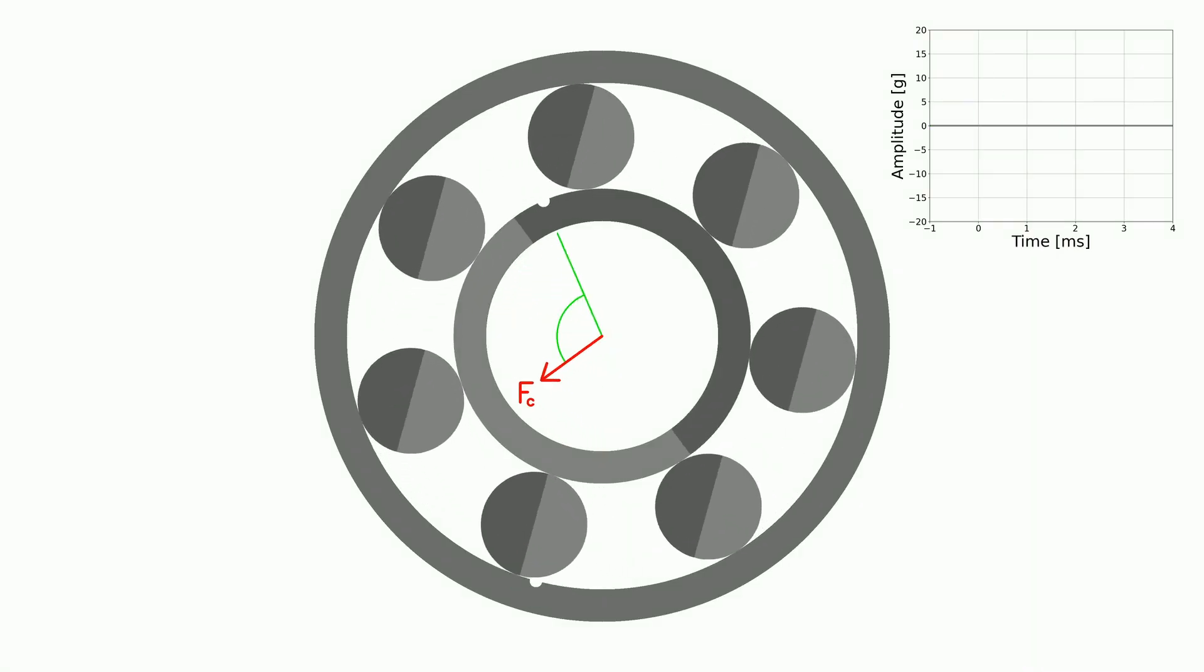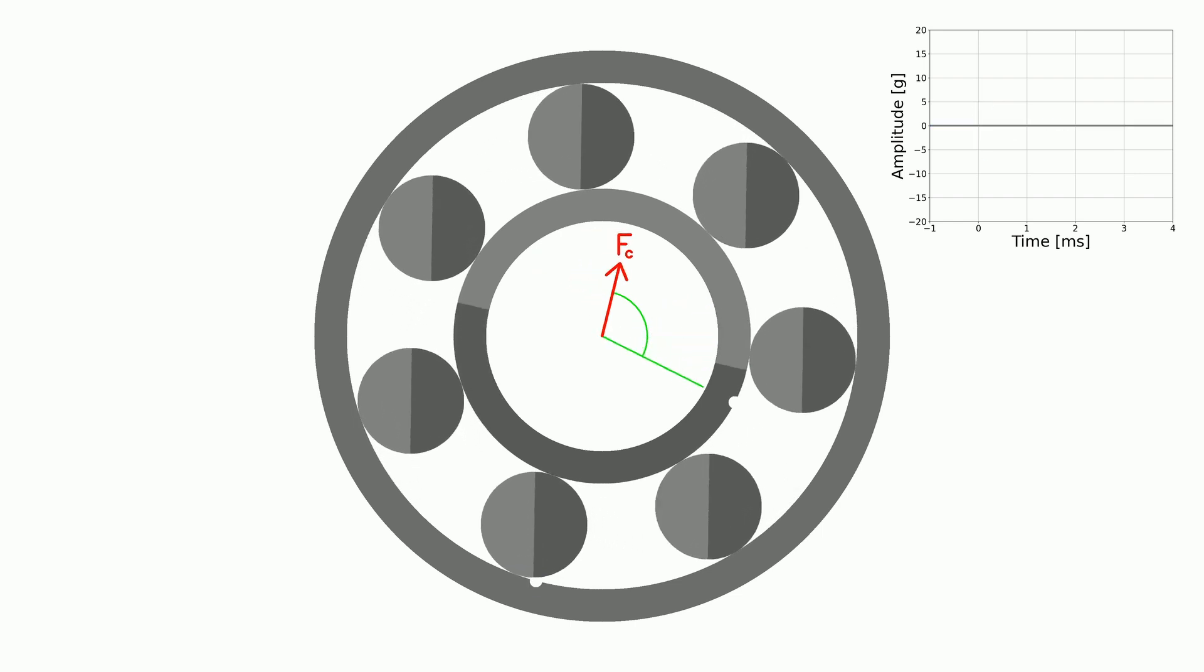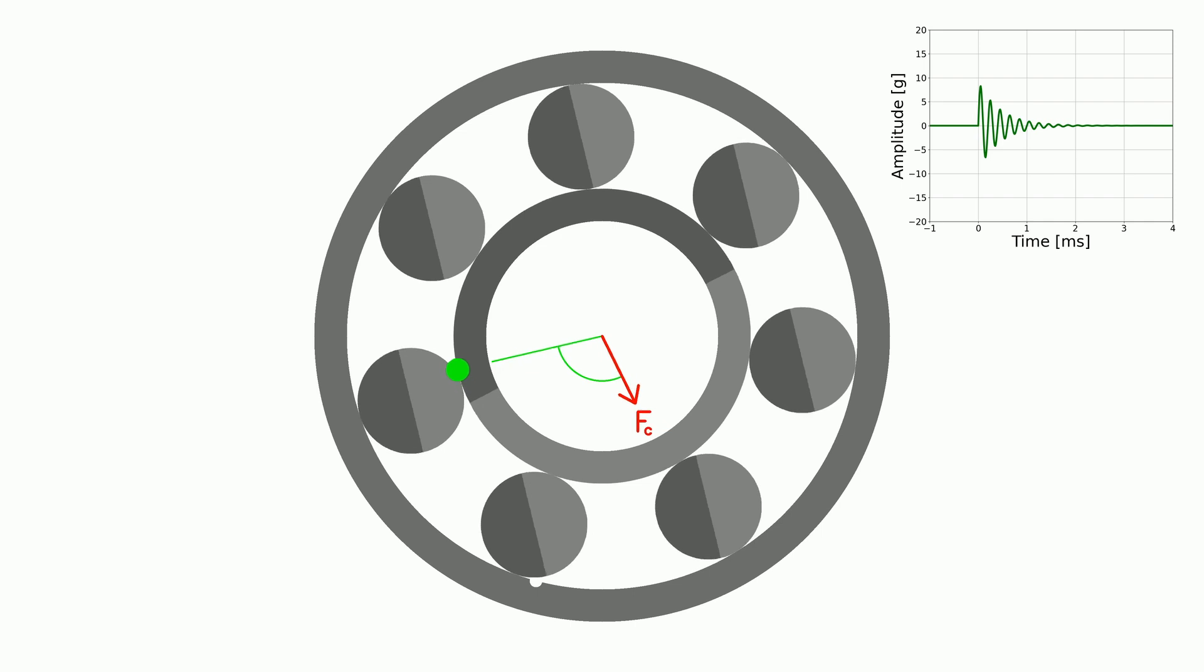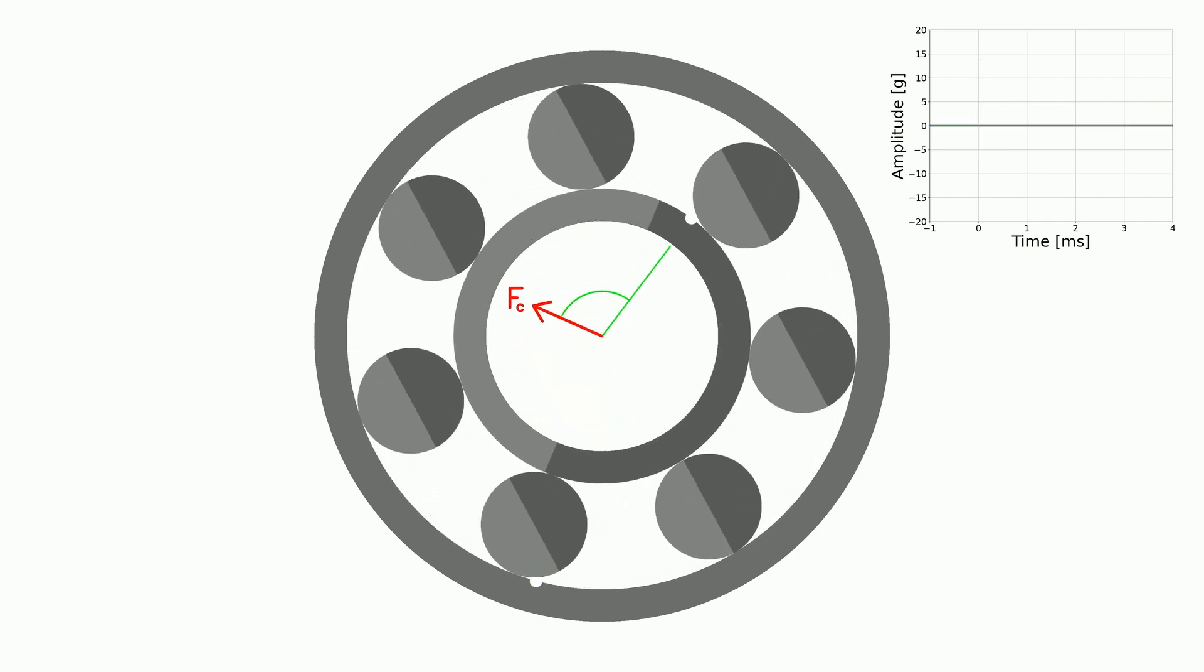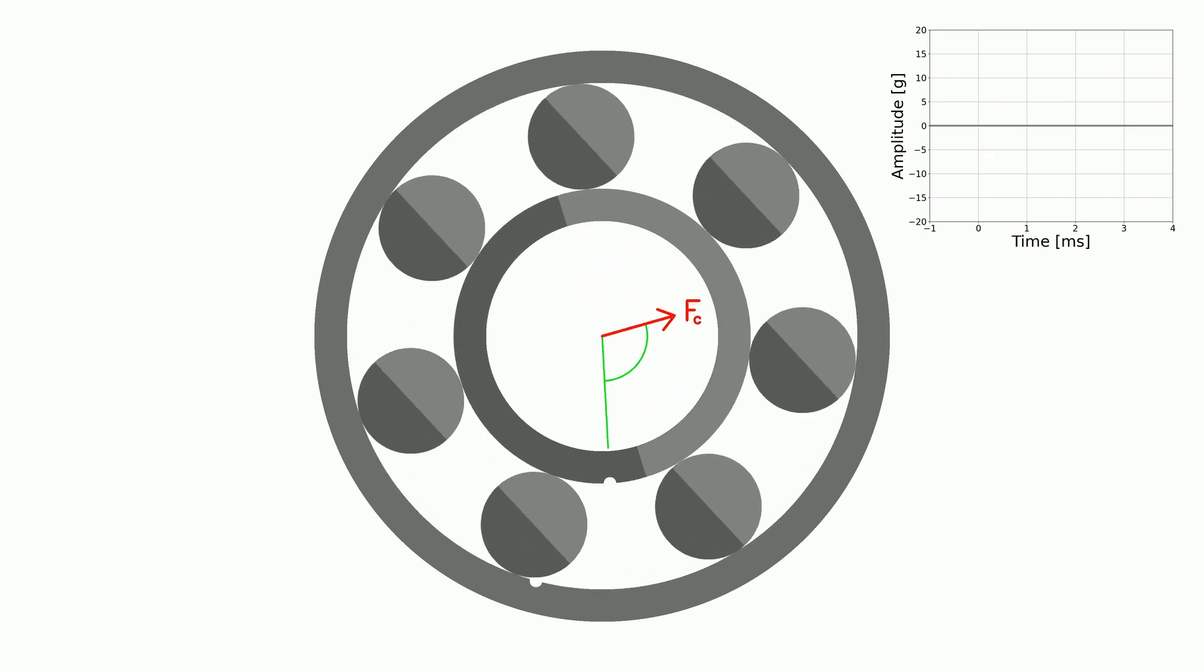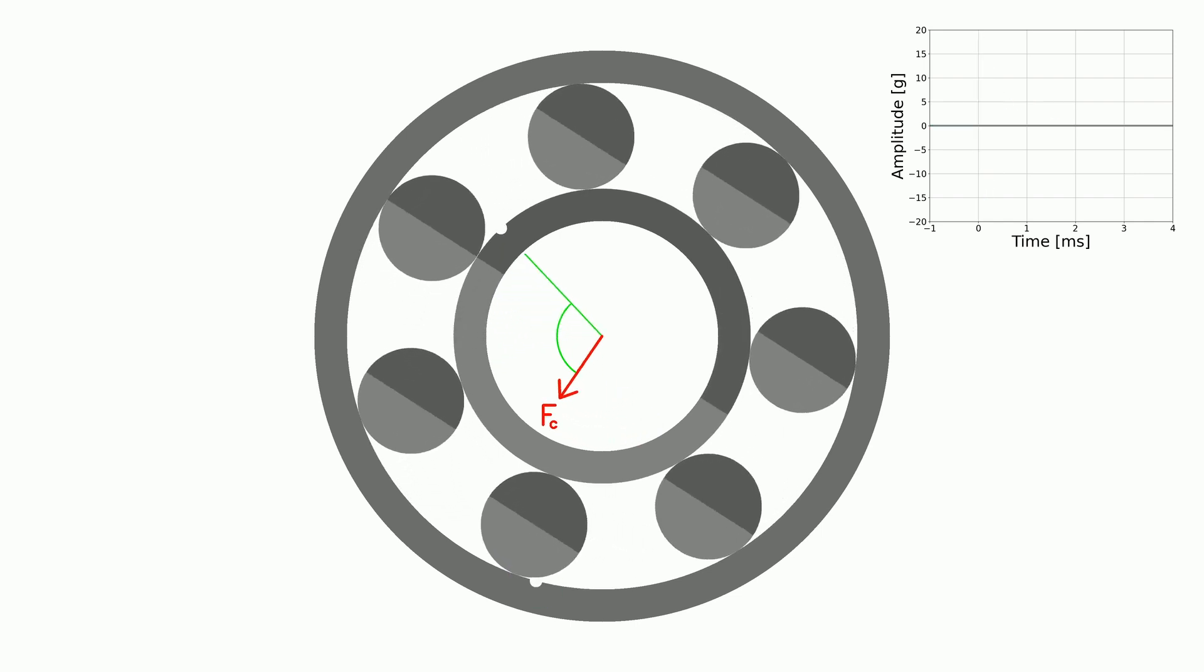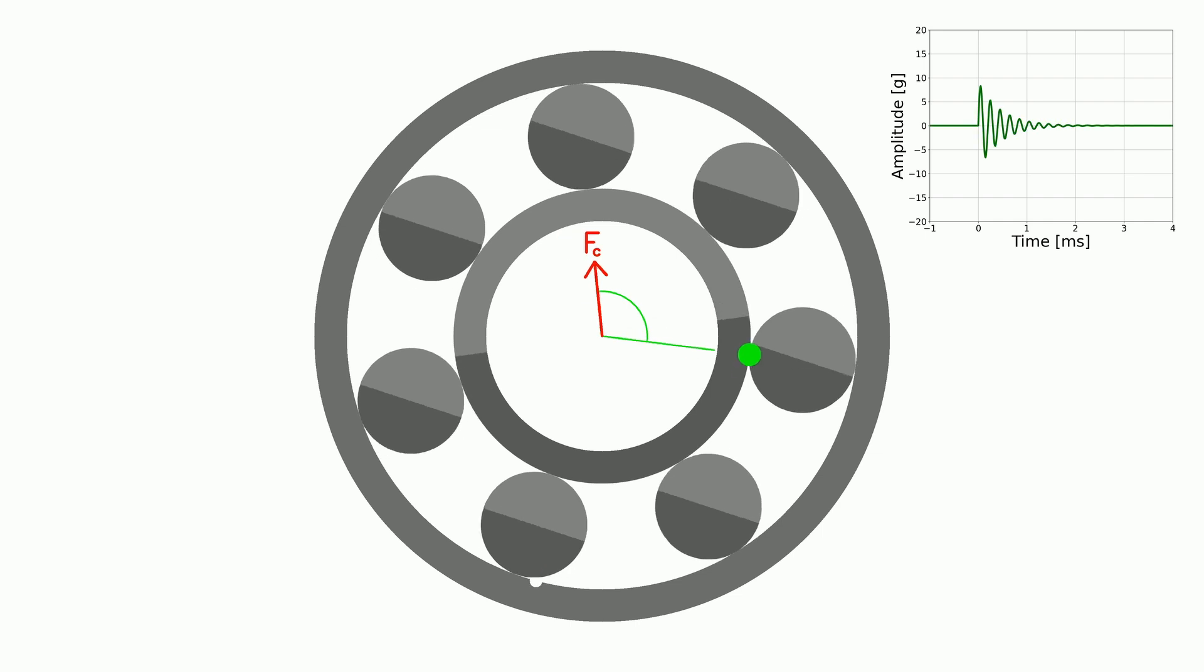This is what it looks like if there is a fault on the outer race and on the inner race. The outer race shocks are modulated like in the previous example. The inner race shocks are not. Because the fault on the inner race rotates with the shaft. Therefore, the force acting on the fault is always the same.